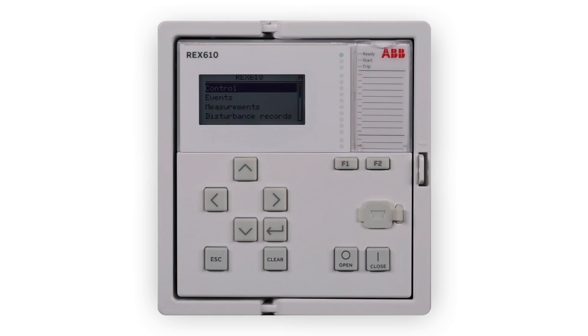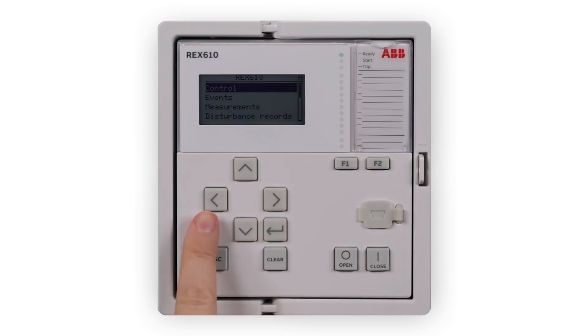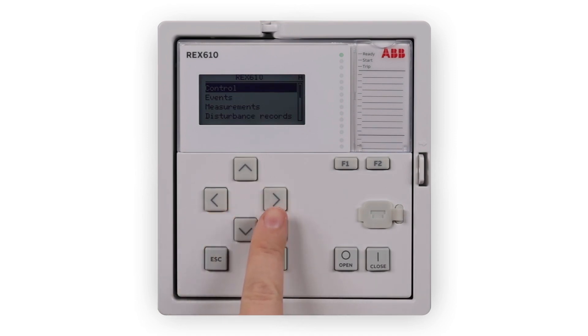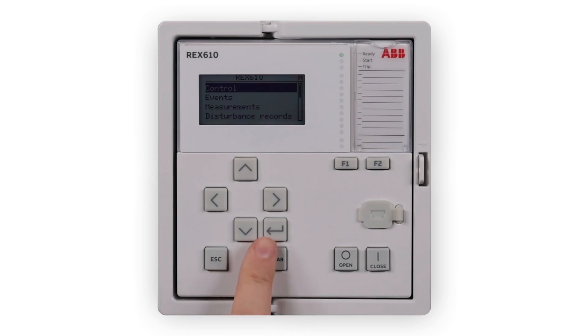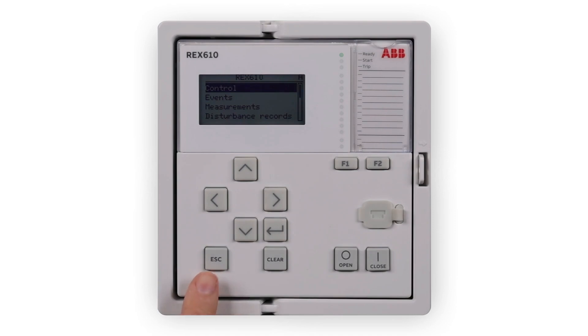The arrow keys are used for navigating the menus of the relay and changing the setting value. Up and down for moving up and down in the menus; left and right arrows are used when moving left and right in menus. Enter key is used for entering parameter setting mode and confirming a new value of a setting parameter. It can also be used to initiate the login screen if local override is set to false. ESC or escape button is used for cancelling certain actions, like leaving a setting mode without changing the value.